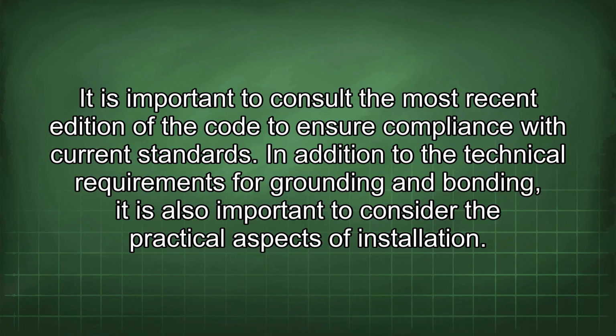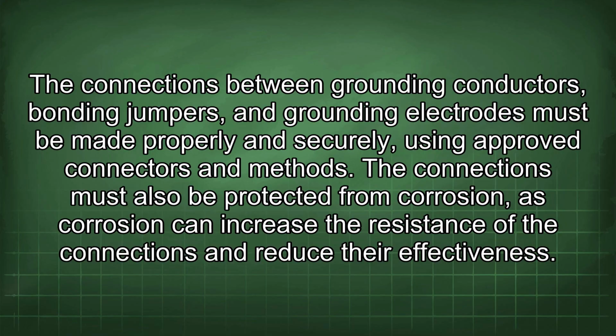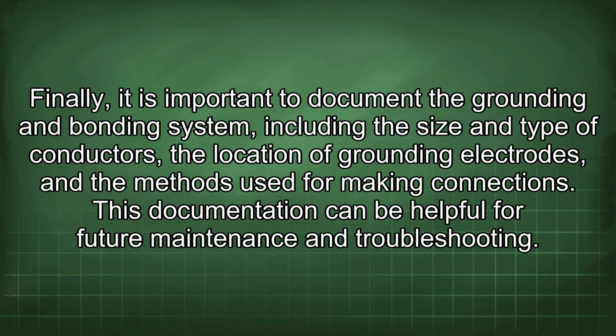In addition to the technical requirements for grounding and bonding, it is also important to consider the practical aspects of installation. The connections between grounding conductors, bonding jumpers, and grounding electrodes must be made properly and securely, using approved connectors and methods. The connections must also be protected from corrosion, as corrosion can increase the resistance of the connections and reduce their effectiveness. Finally, it is important to document the grounding and bonding system, including the size and type of conductors, the location of grounding electrodes, and the methods used for making connections. This documentation can be helpful for future maintenance and troubleshooting.